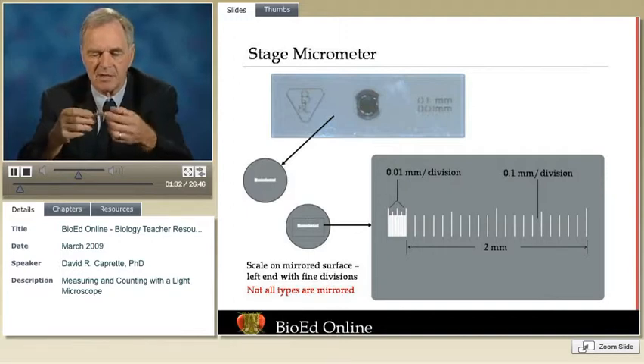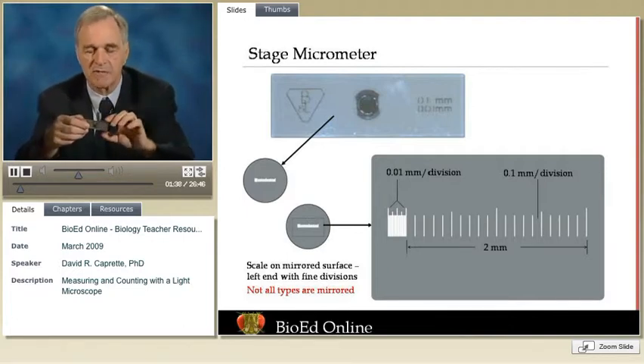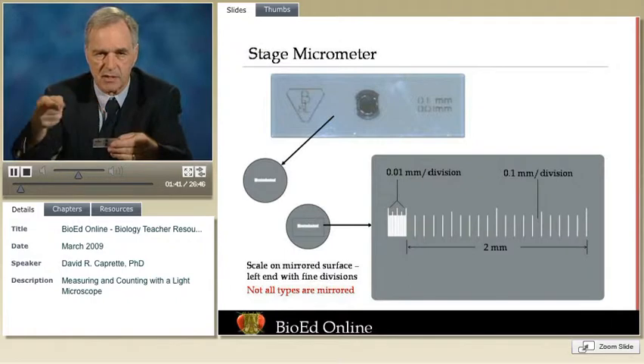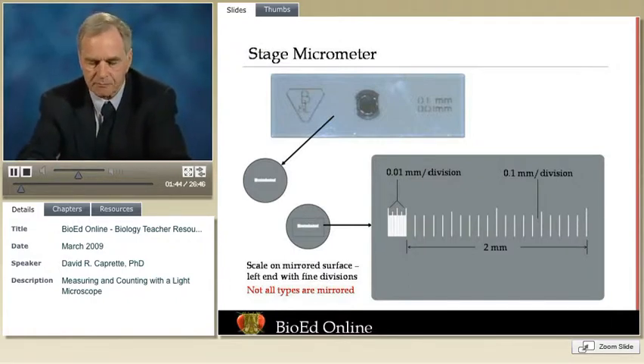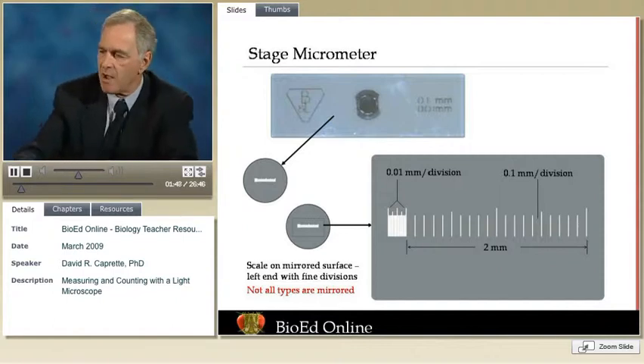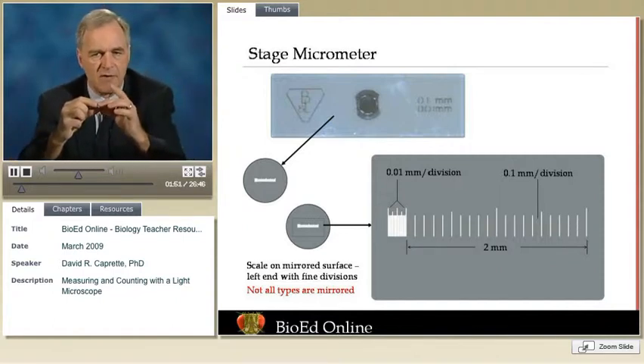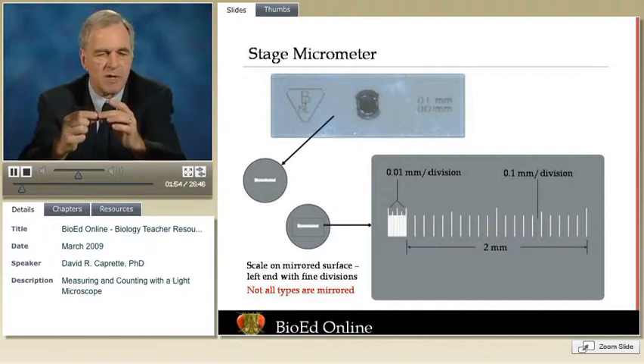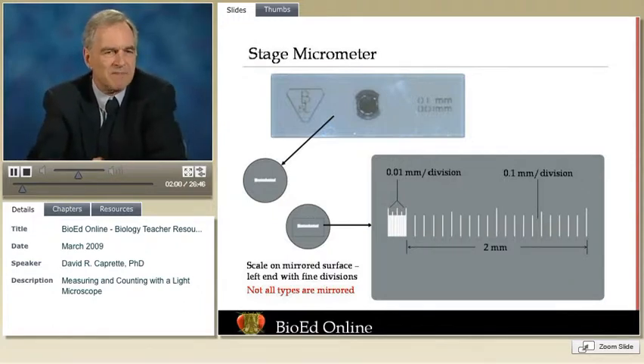A stage micrometer is a ruler that's placed on a modified glass slide. It's usually a very thick slide. It may have a mirrored surface, or it may be a clear surface with etchings that are engraved and shaded. Whatever it is, the stage micrometer acts as a tiny, very, very accurately etched ruler, usually 2 millimeters wide, maybe 2.5 or so. And usually, because the calibration marks are so difficult to make precisely, and because the technique used to be very expensive, maybe it still is, one end and one end only will be etched to very, very fine markings. Typical stage micrometer would be about 2 millimeters wide.